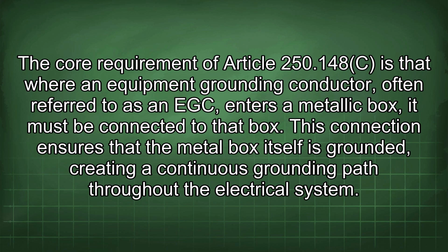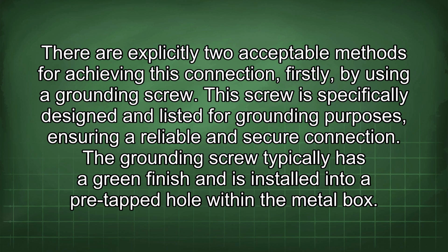The core requirement of Article 250.148C is that where an equipment grounding conductor, often referred to as an EGC, enters a metallic box, it must be connected to that box. This connection ensures that the metal box itself is grounded, creating a continuous grounding path throughout the electrical system. There are explicitly two acceptable methods for achieving this connection.